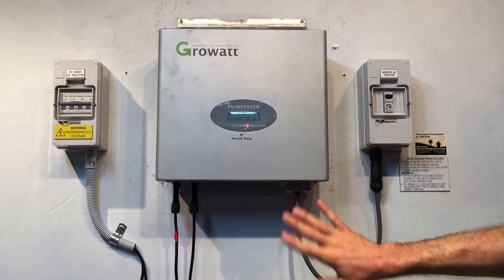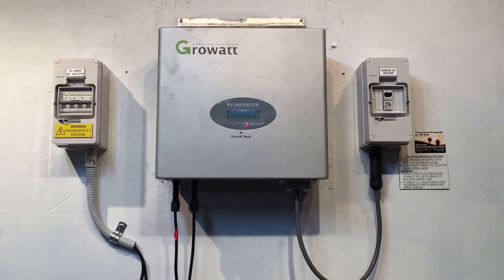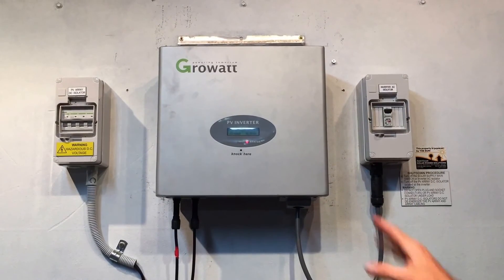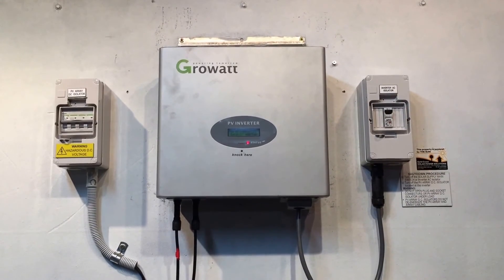What they're going to need to do is check that you're actually getting the right voltage from the electricity grid into the inverter. If you're not, we know it's a problem with the circuit breakers or some of the connections. If you are getting power there, we know it's an issue with the actual inverter, which will need to be looked at.